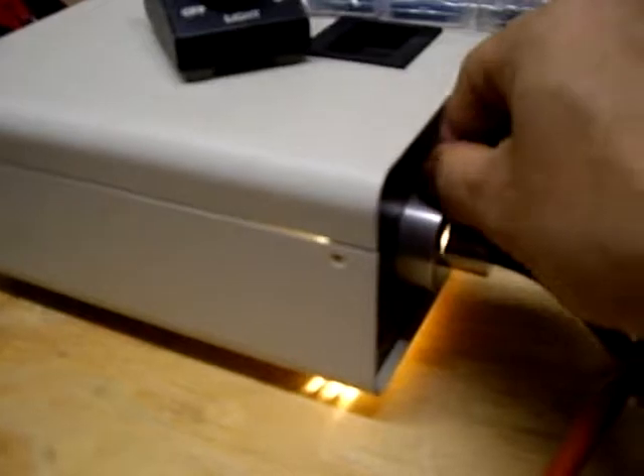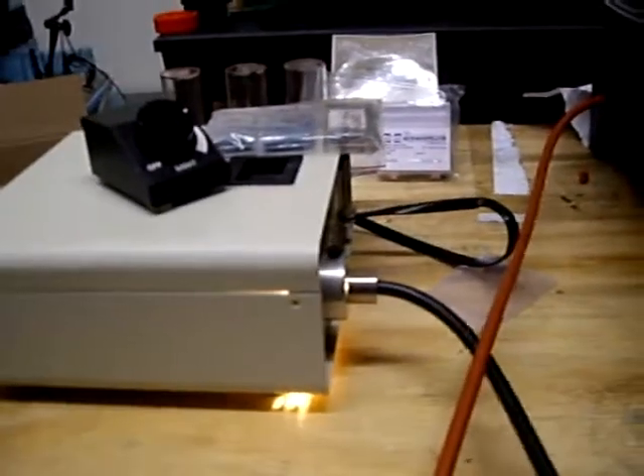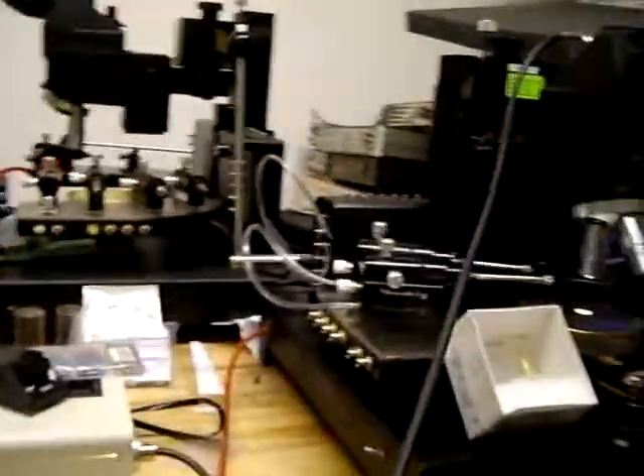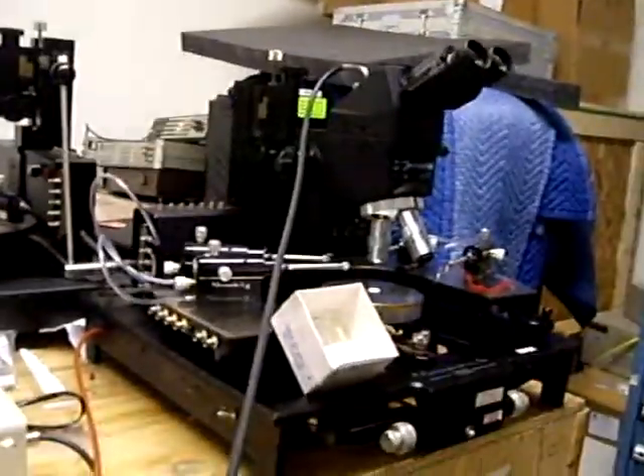You see, I plug in the fiber optic cable. This is the fiber optic cable, this one here, and this one goes all the way to the top of the microscope here. Okay, and when it's on, you can see the light come out. You plug that in top of the microscope, okay, and you turn the screw, and that will tighten the fiber optic cable. On one end it connects to illuminator, on the other end it connects to the microscope on the probe station. Okay, now let's set this aside.